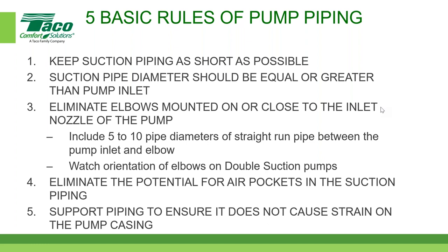We try to keep the suction piping as short as possible. Suction pipe diameter should be equal or greater than the pump inlet, right? So you don't want to be restricting things there. That causes flow issues going in there. And then try to eliminate as many elbows mounted on or close to the inlet nozzle of the pump. And we recommend 5 to 10 pipe diameters. You know, there are different numbers out there of straight run of pipe between the pump inlet and elbow, or that suction diffuser. Although that could have been one of the worst things ever made for pumps, to be quite honest. And then we're not talking double suction pumps today, but watch orientation of elbows, and we can get into that in another presentation.